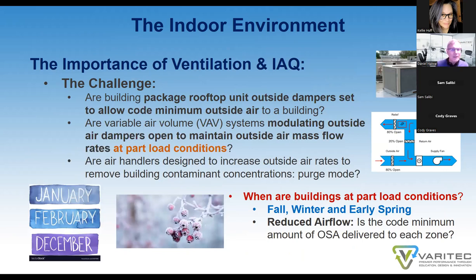So that being said, when we design an HVAC system, more often than not, these systems are designed to provide minimum ventilation rates prescribed by the standard, not ideal rates, minimal rates. And consequently, if you design to the minimum and you have a building that's been in operation for a while, a building owner should ask the question, are package rooftop DX unit outside air dampers set to allow at least the minimum amount of outdoor air into a building to reduce the risk of infection? That was one of the prescriptive measures the Epidemic Task Force advocated for, is to make sure the outside air damper is properly set on those mixed air units.